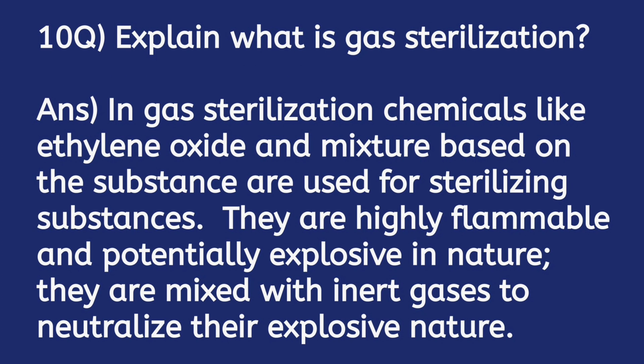What is gas sterilization? In gas sterilization, chemicals like ethylene oxide and mixtures based on the substance are used for sterilizing substances. They are highly flammable and potentially explosive in nature, so they are mixed with inert gases to neutralize their explosive nature.